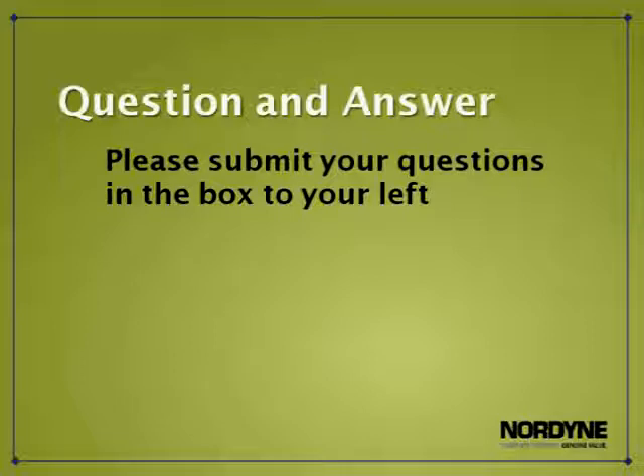Next question from Dave. What is the purpose of the limit circuit? As I mentioned earlier, the limit circuit is there to protect the furnace from overheating. Now, there are a number of different limits within our furnace. We'll start out with the heat exchanger limit. The heat exchanger limit is there, as stated, to protect the heat exchanger from overheating, getting too hot, and possibly damaging some other components within the furnace. All of the limits have their maximum rating, their open rating, on the limits themselves.